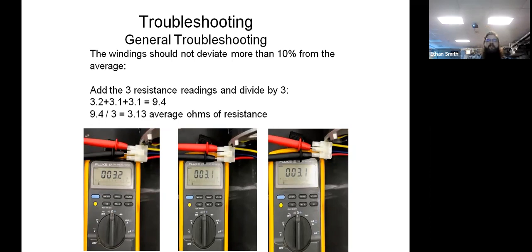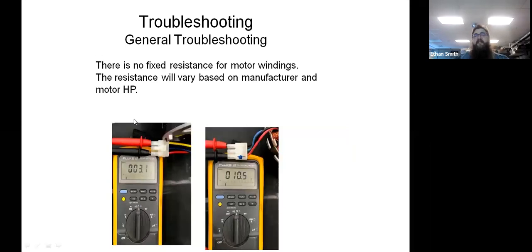If you have an open line or you've got an imbalanced motor, you probably need to have that motor replaced. Usually when that happens to a motor, it's going to take the drive with it, so you're going to need to replace that end bell at the same time. So you replace both components of the motor in that case. There isn't a fixed resistance for motor windings. So we've got 2 different motors that we tested here. This is a 3.1 resistance winding. This is a larger motor, and that's going to have 10.5 ohms of resistance. So it's not so important what that reading is, but that it's within 10% of everything else. Any questions, guys?